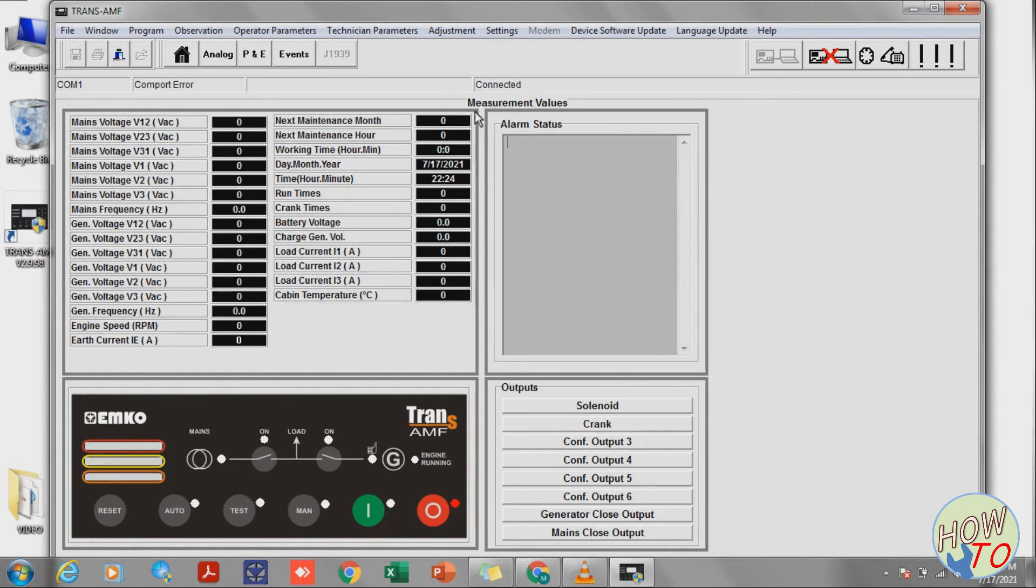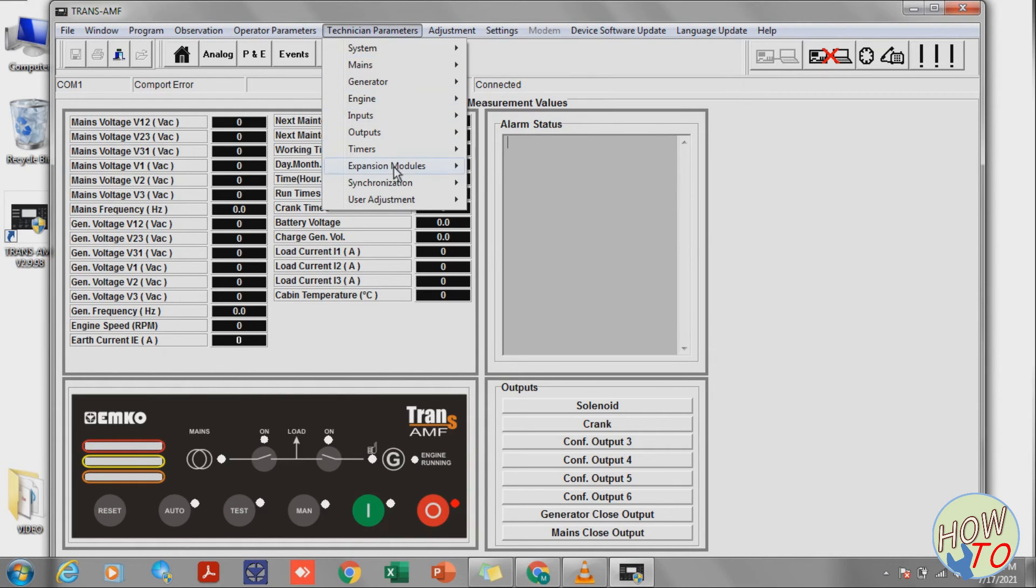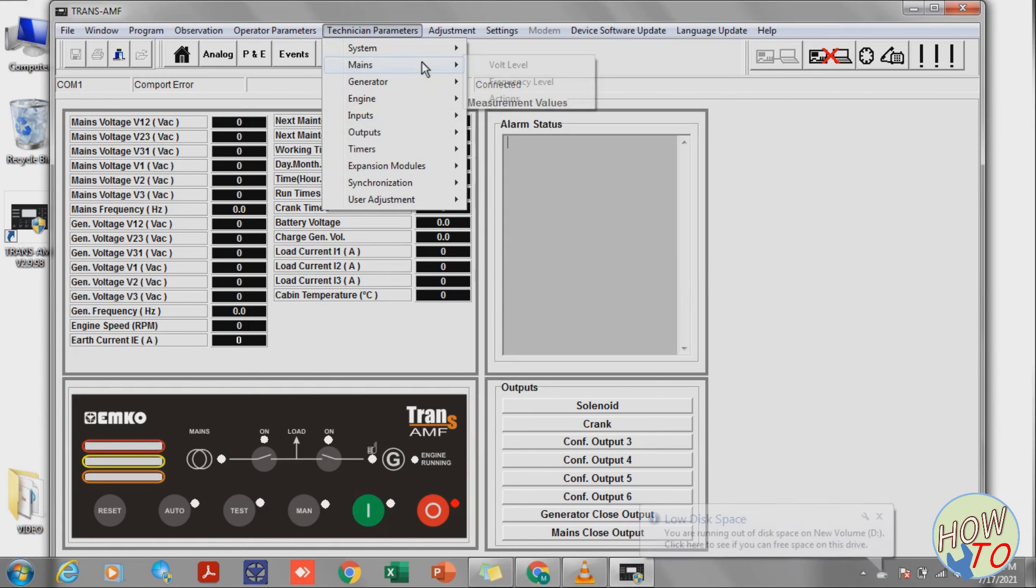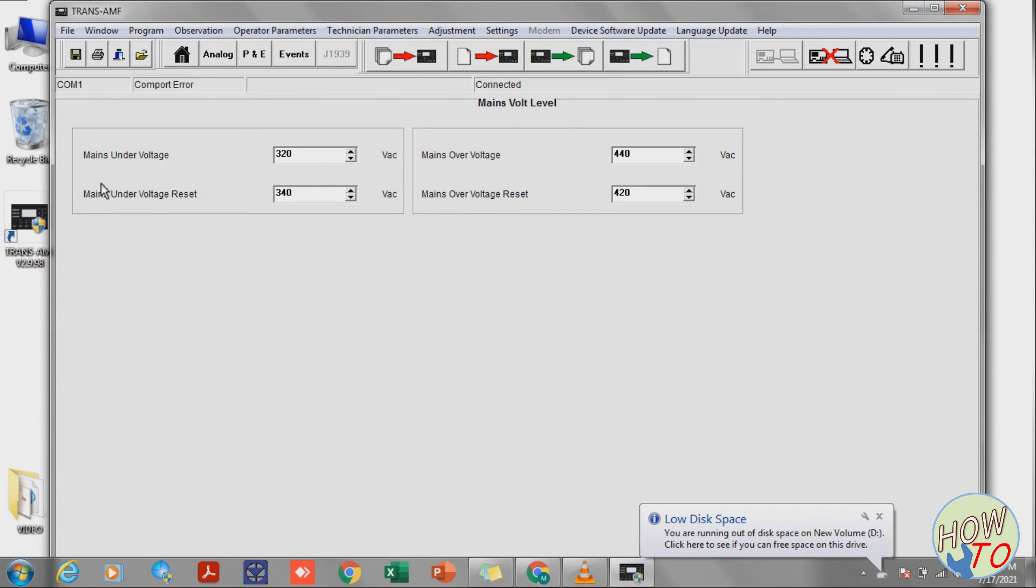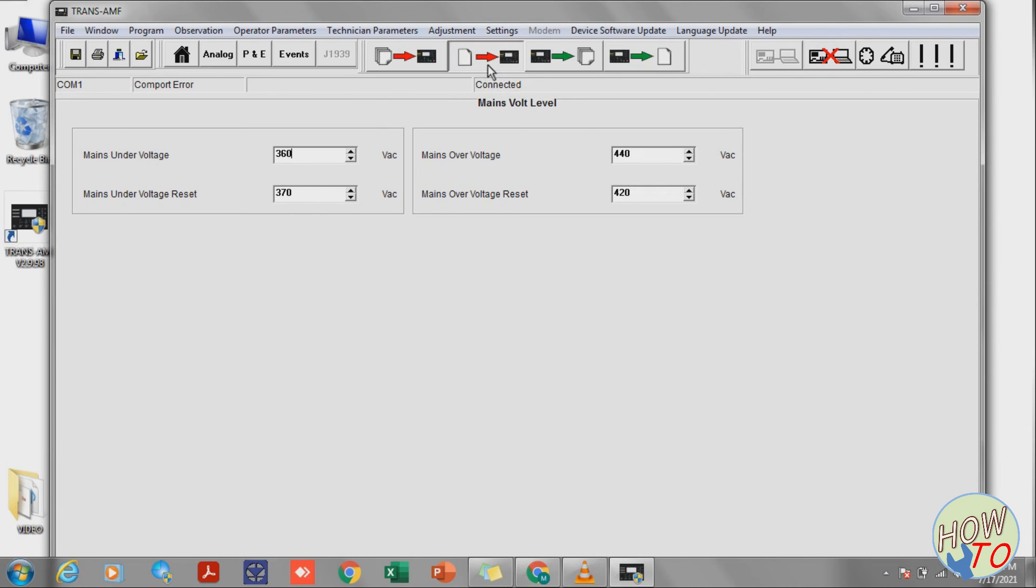Now it's connected and the status is shown here. You can go to Technician Parameters. From here you can program anything. For example, you can go to Main Voltage and define the voltage you require. Undervoltage you require is 360, and reset you need is at 370. After that, you can send the file.